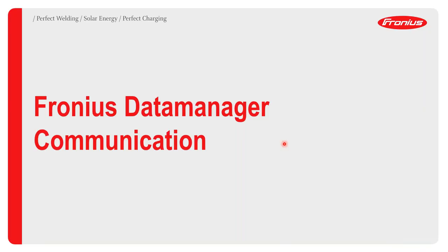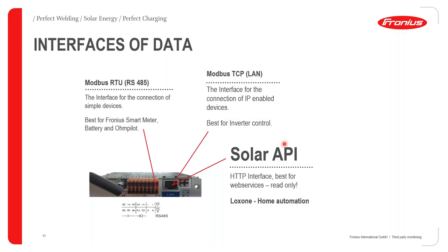Now let's look at how the Data Manager communicates via its communication interfaces. For the Modbus RTU, this interface is used for the connection of simple devices — it is best used for connection of the Fronius Smart Meter, battery, and Ohmpilot.